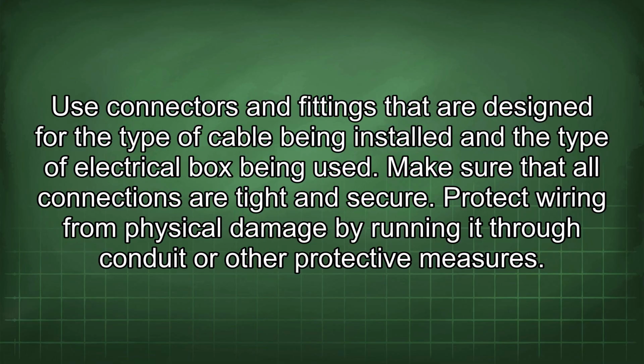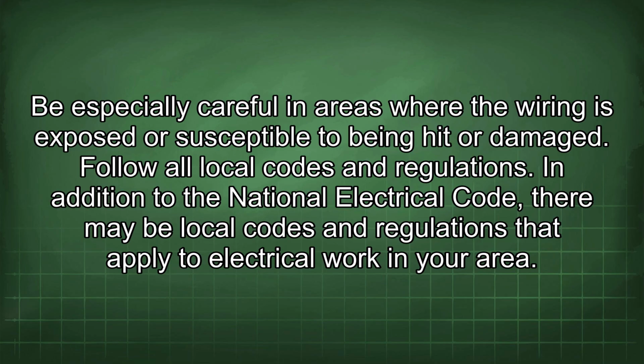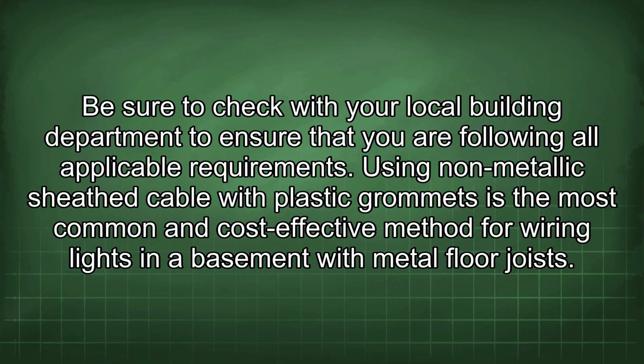Protect wiring from physical damage by running it through conduit or other protective measures. Be especially careful in areas where the wiring is exposed or susceptible to being hit or damaged. Follow all local codes and regulations. In addition to the National Electrical Code, there may be local codes and regulations that apply to electrical work in your area. Be sure to check with your local building department to ensure that you are following all applicable requirements.